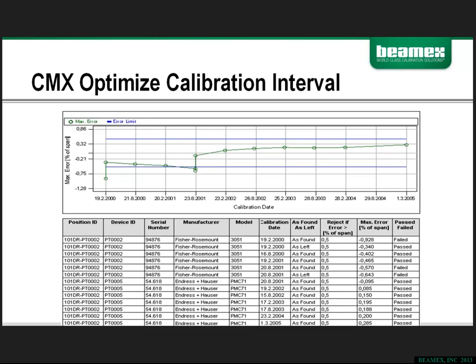So if you look just below that, you see as left data, which shows that it was performed on the same date as the rejection error. Once it was adjusted, it met 0.340% of span, which is well inside the 0.5% that was specified by the manufacturer. So at that point, that asset was considered to be passing.